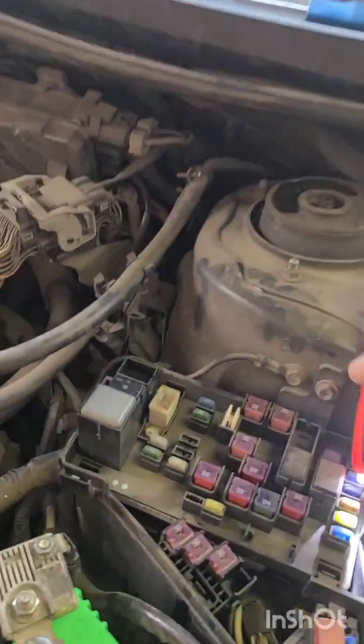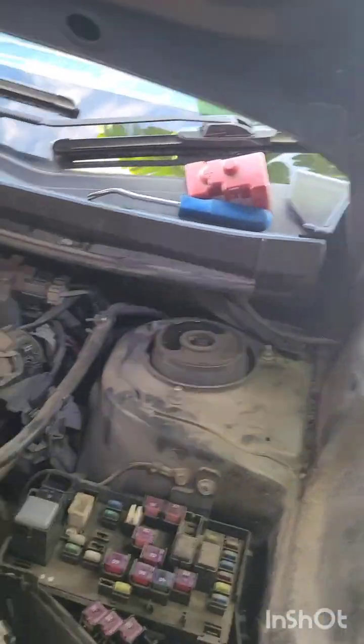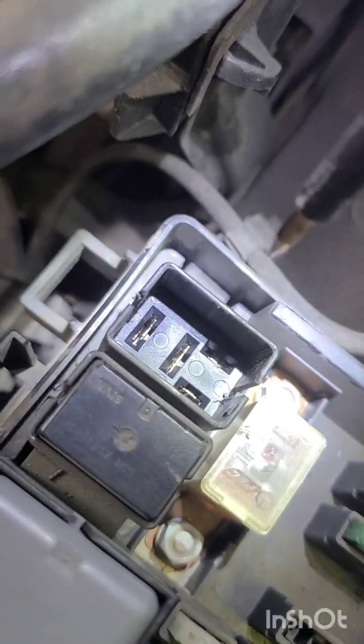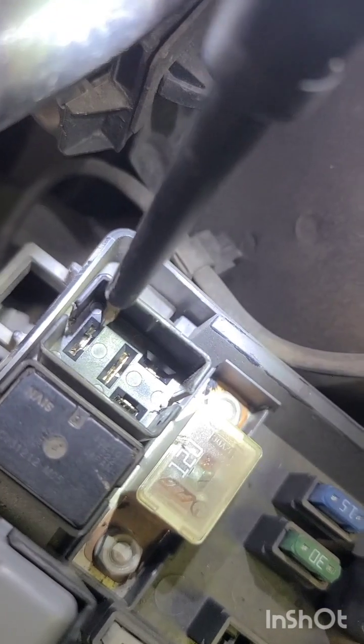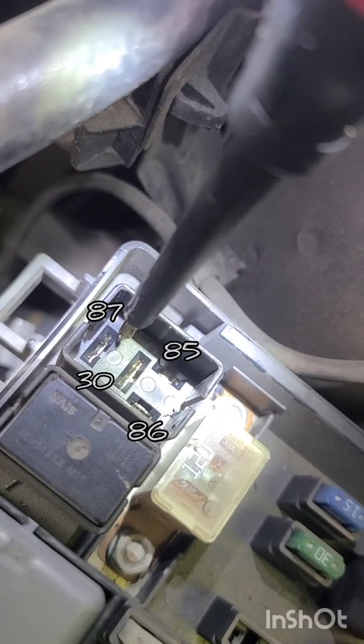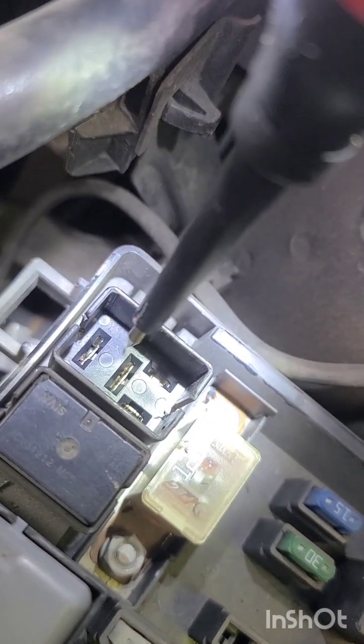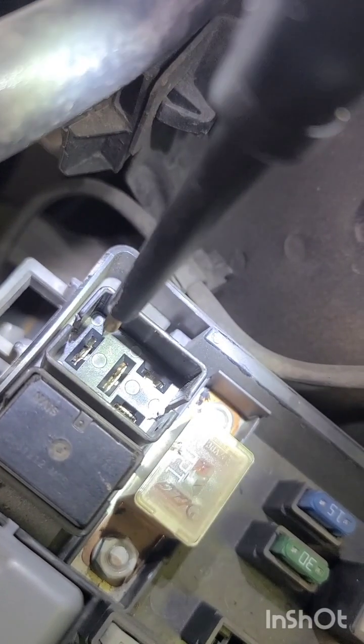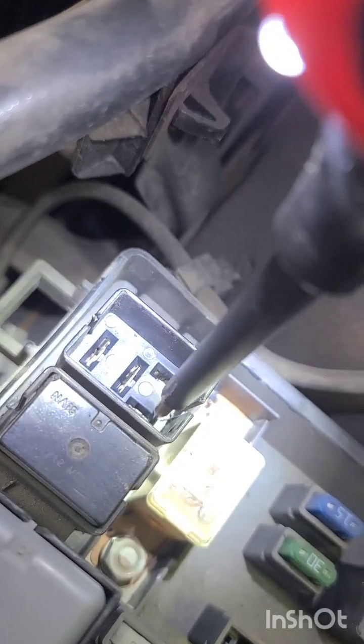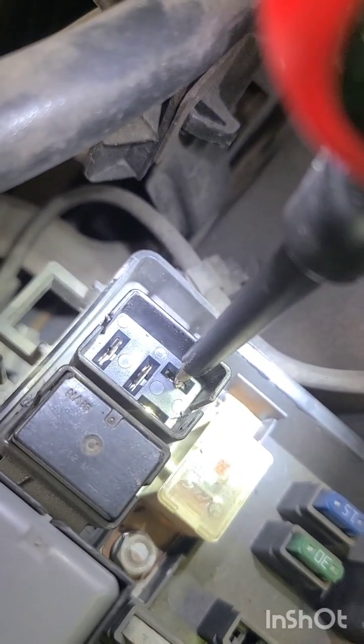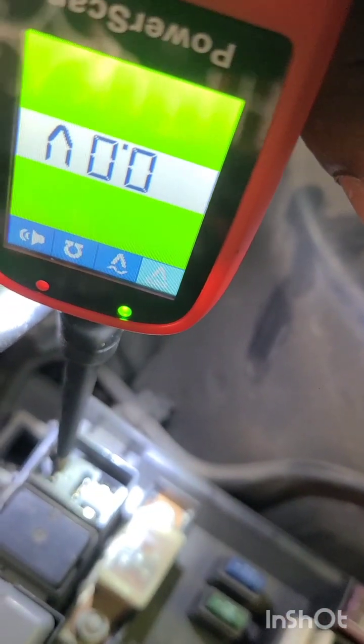When testing a relay, normally we check the terminals. These two should be the ones that go to the load - one of these should have a positive circuit that, when closed in the relay, sends current out to the negative, going to the headlight bulb in this case. Then we have the two for the coil in the relay; when these are energized, it closes the loop and sends current to the load. One of these should give us positive - this one is positive, and this is negative.